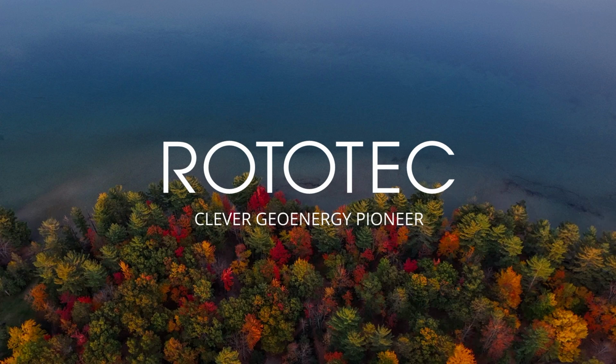Just a couple of brief comments before we bring up Stuart Lyle from ISCO. I'm not sure if anyone in the audience had picked up on a couple of vast differences from Sweden to the US. A couple of things that I picked up were just the sheer size of the pipe, right? And going from an SDR11 or an SDR9 for the loops to an SDR17. So those are some design considerations we need to think about, as well as the way that we were fusing the pipe. In Sweden, they were discussing doing electrofusion.